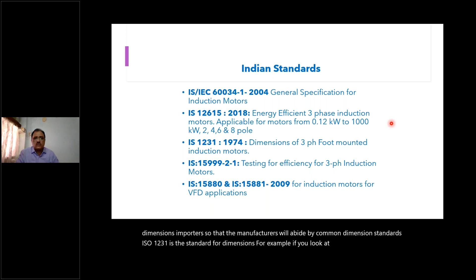Similarly, India is the only country which has put a restriction on boundary dimensions of motors, so that the manufacturers will abide by common dimension standards. IS 1231 is the standard for dimensions. If you look at some of the slides in the future, you will appreciate that all the boundary dimensions have to be identical in order to interchange different makes of motors. It should not so happen that different manufacturers have different dimensions and the consumer is compelled to use that particular make only. This is to ensure that monopolistic, restrictive trade practices are not practiced by the motor manufacturers. IS 1231 is a very important tool.